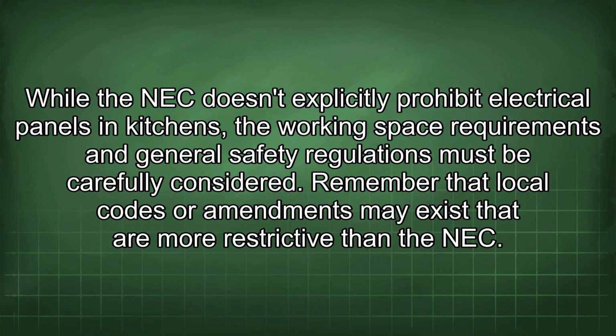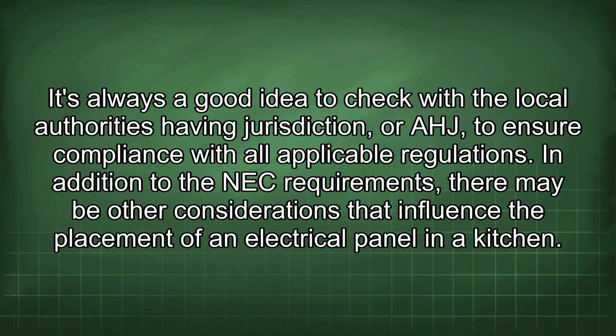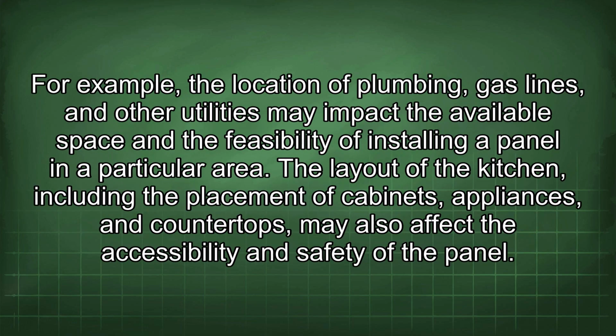While the NEC doesn't explicitly prohibit electrical panels in kitchens, the working space requirements and general safety regulations must be carefully considered. We must remember that local codes or amendments may exist that are more restrictive than the NEC. It's always a good idea to check with the local authorities having jurisdiction to ensure compliance with all applicable regulations. In addition to the NEC requirements, there may be other considerations that influence the placement of an electrical panel in a kitchen. For example, the location of plumbing, gas lines, and other utilities may impact the available space and the feasibility of installing a panel in a particular area.